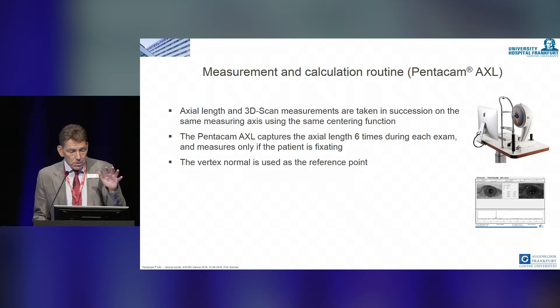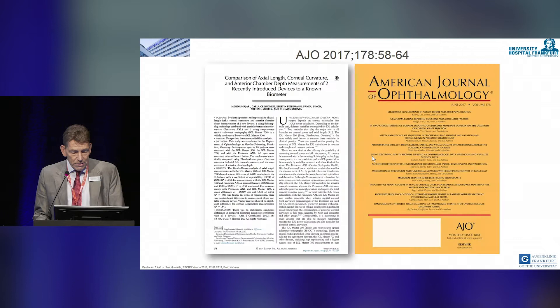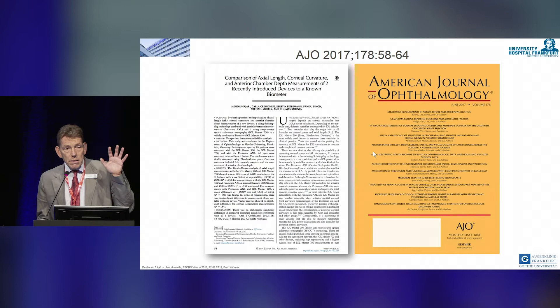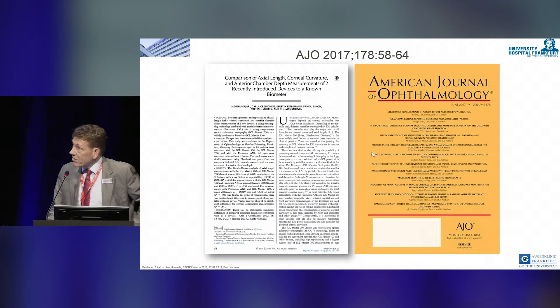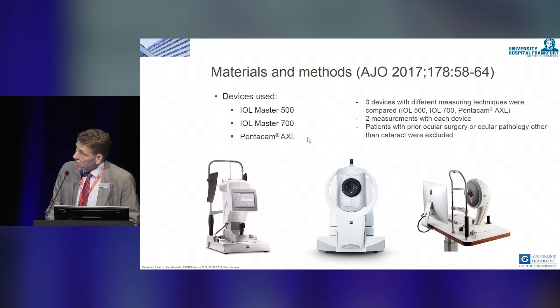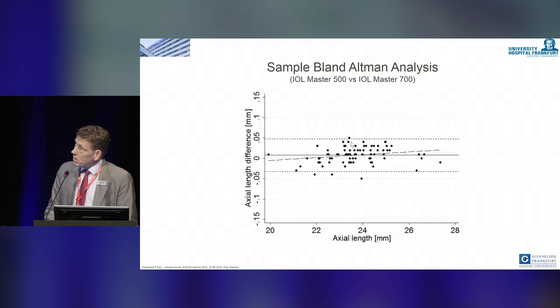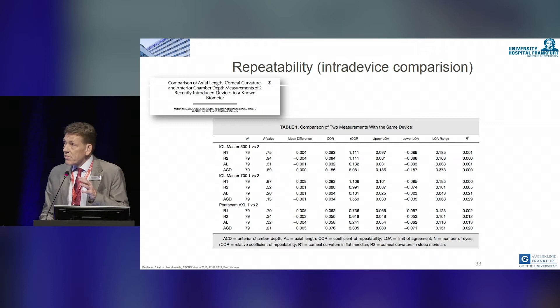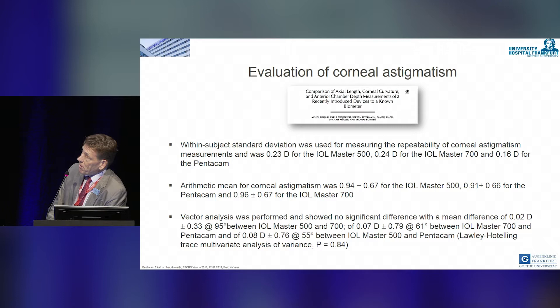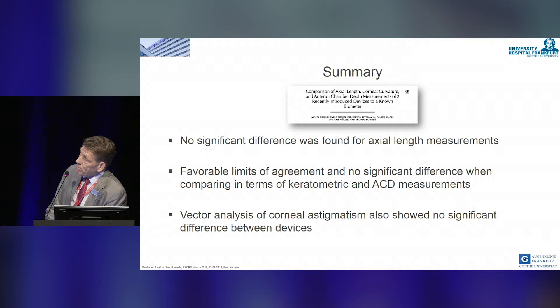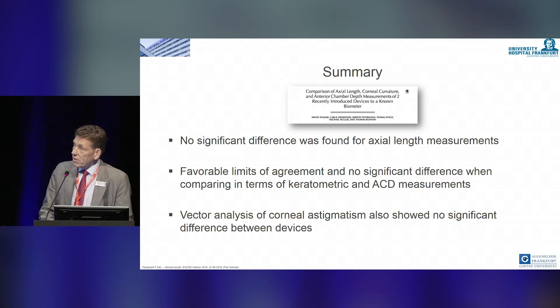We published a paper in AJO looking at the difference between IOL Master 500, IOL Master 700, and the Pentacam AXL, doing these axial length measurements. In this prospective case series of 79 eyes, we did a Bland-Altman analysis. We found no significant difference for axial length measurement, favorable limits of agreement, and no significant difference comparing keratometry and ACD measurements. The vector analysis of corneal astigmatism also showed no significant difference between these devices.